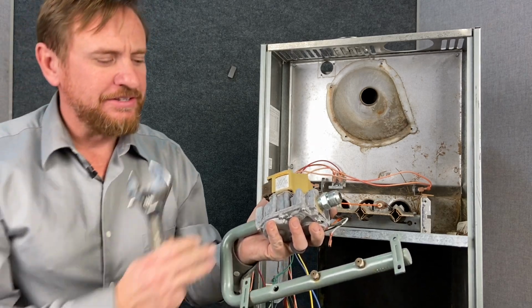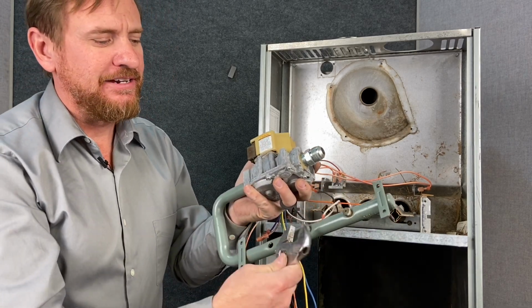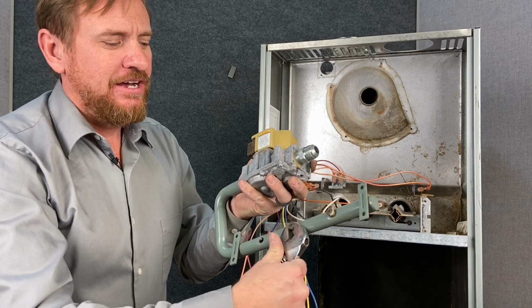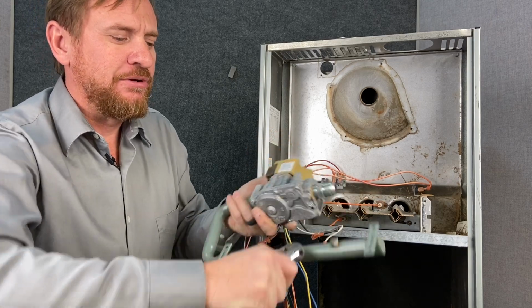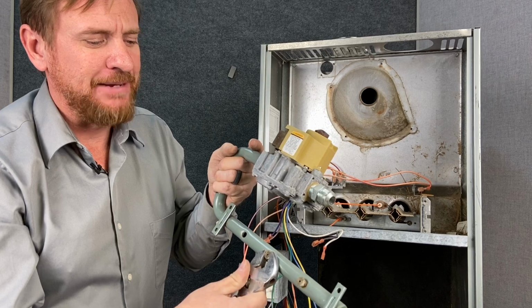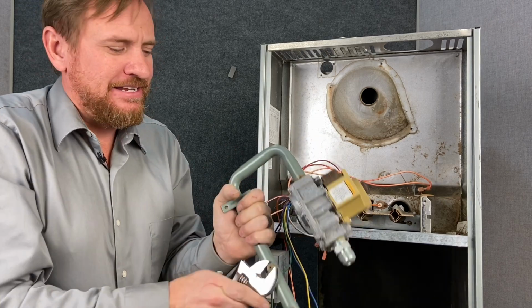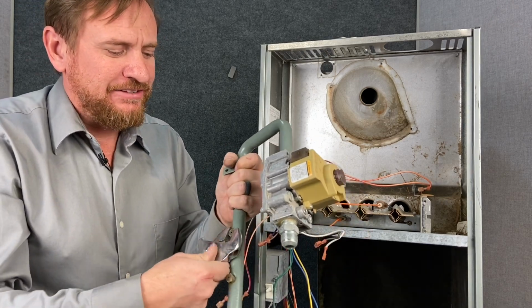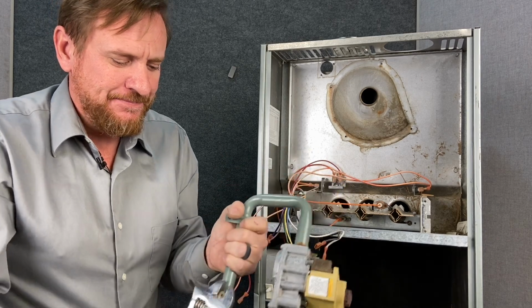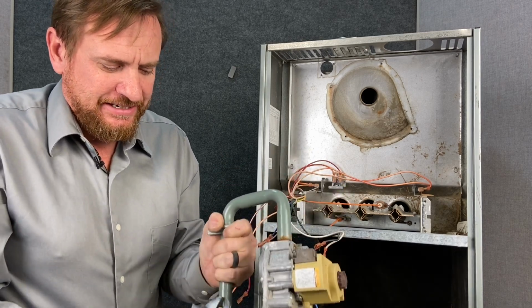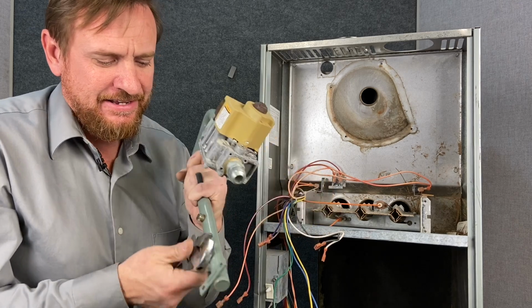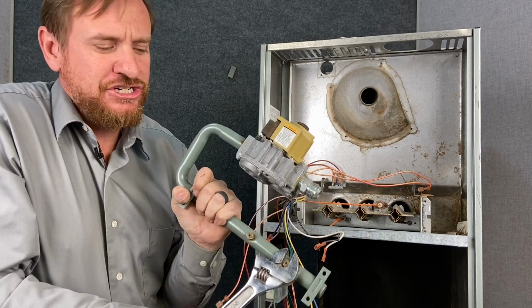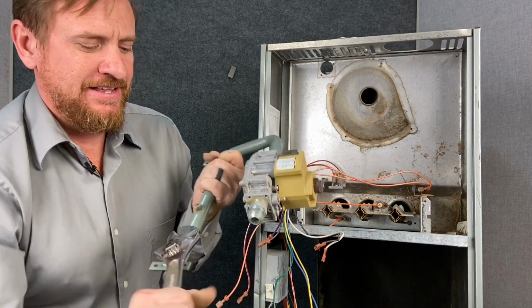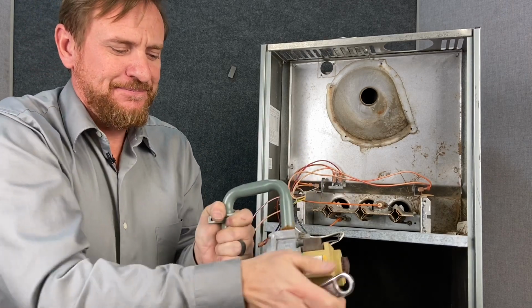But also on this manifold, we have this component right here. And these are usually made of brass, but not always. So we're going to unscrew this, and it has a very special name. And one of the names is called a spud. I have no clue why it's called a spud, but that's the name that we call it. And this one is on there very tight. Try this other one. It's best to use a wrench, especially if it's brass, but this is going into the dump later, so.